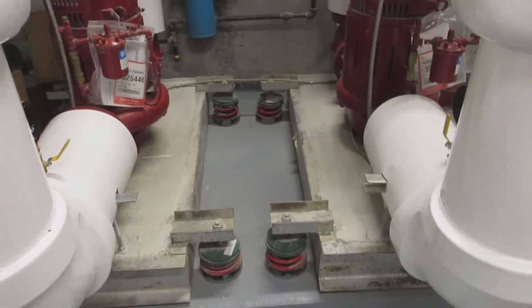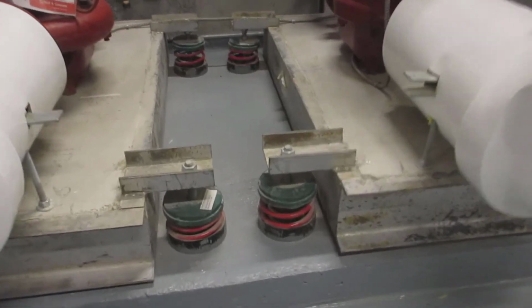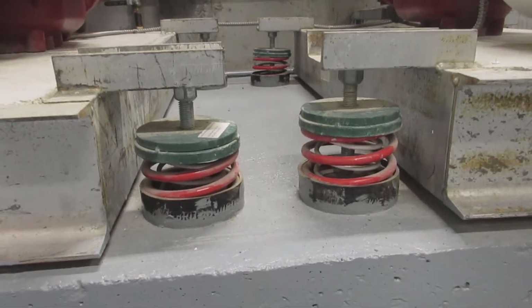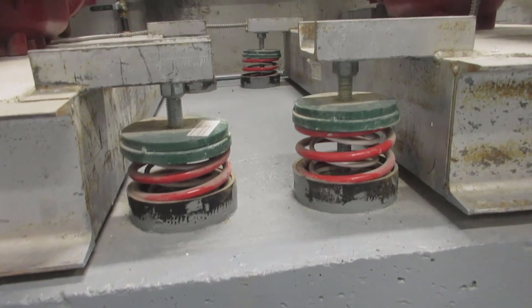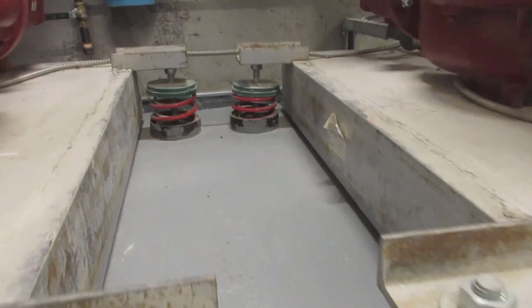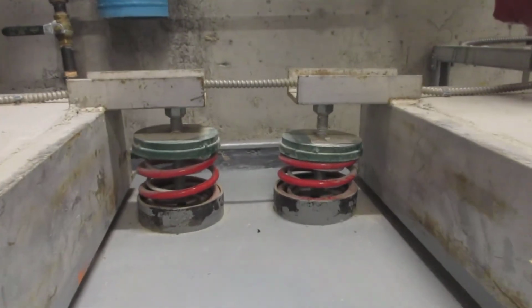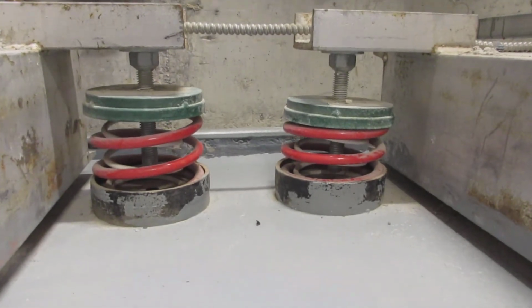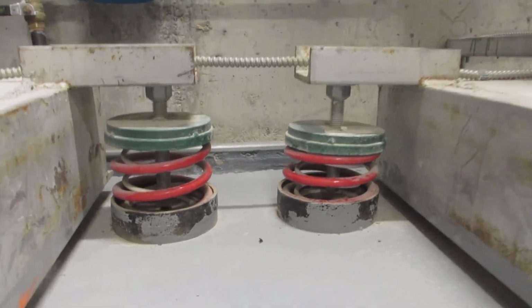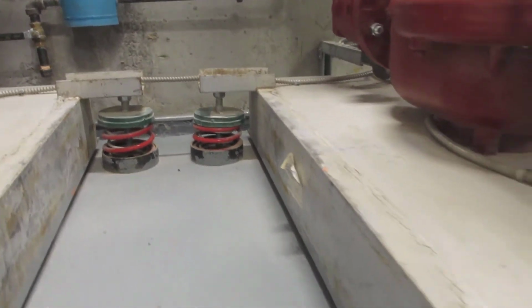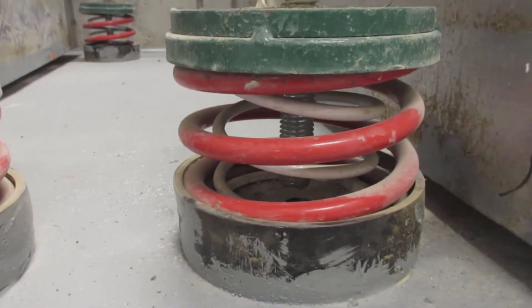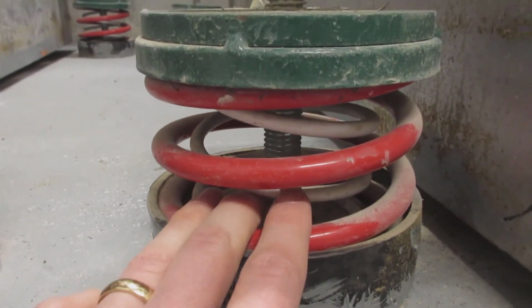The isolators are straight and adjusted and attached to the bases. All the springs have the right colors, red outside and white inside. Moving to the back for a closer look, these isolators also look okay. Minor differences in height like this are not a problem. These springs are nowhere near fully compressed, and if you put your fingers on the coils, you may be able to feel the equipment vibration that is being absorbed by the isolator.